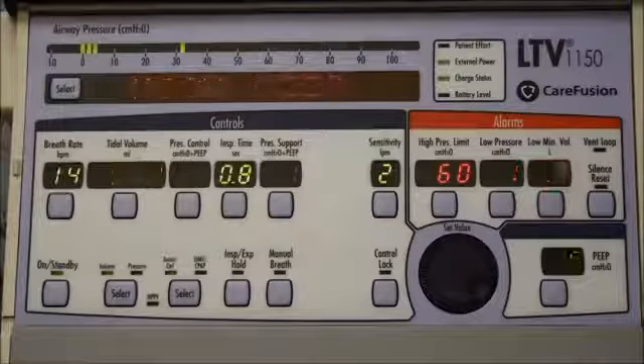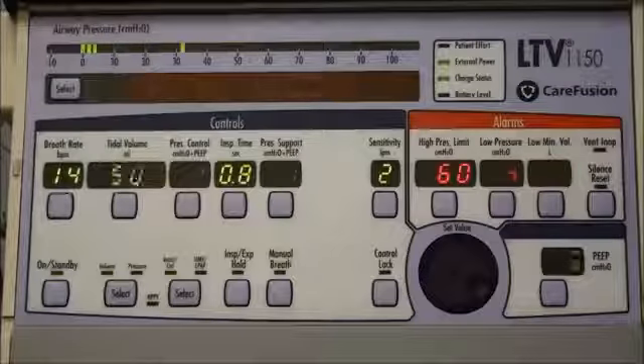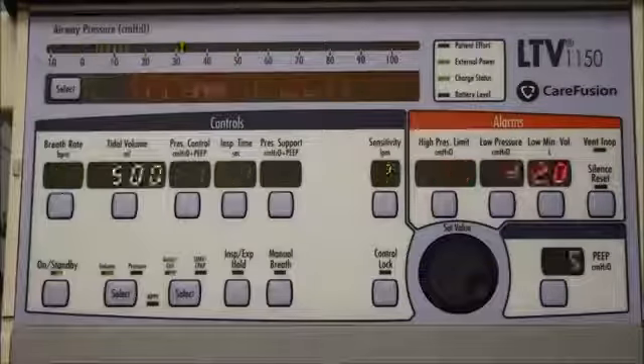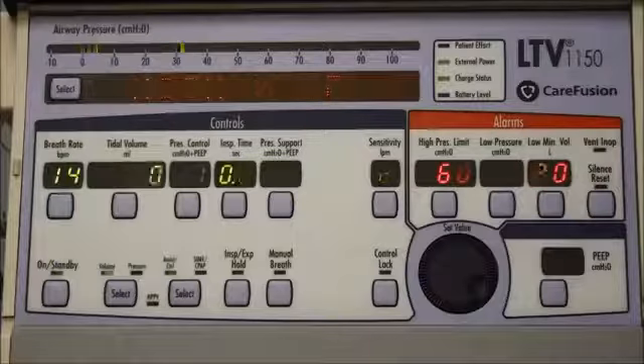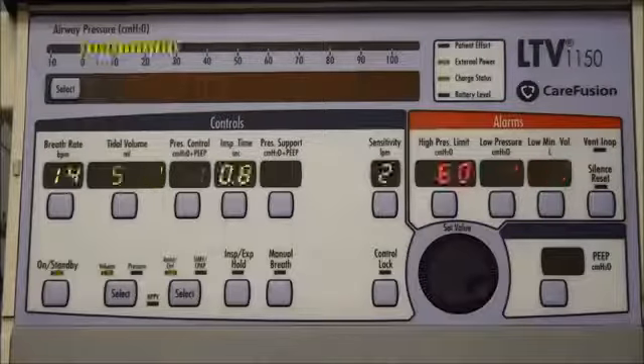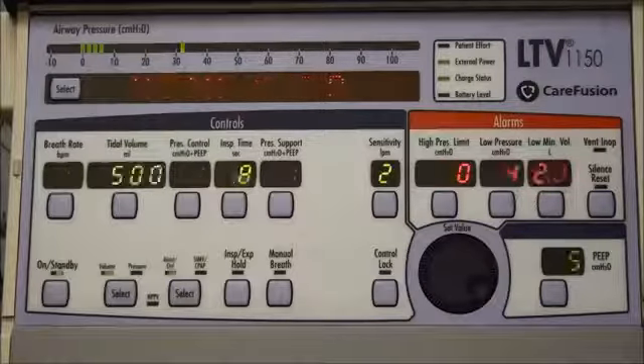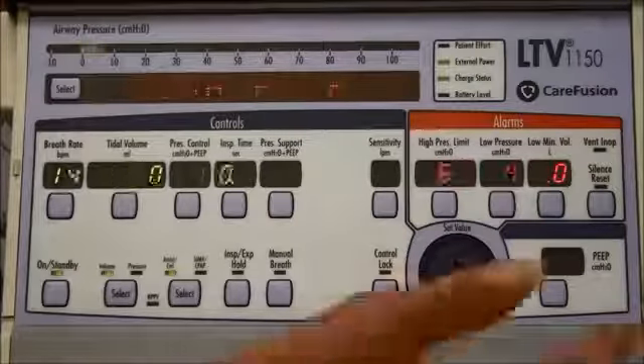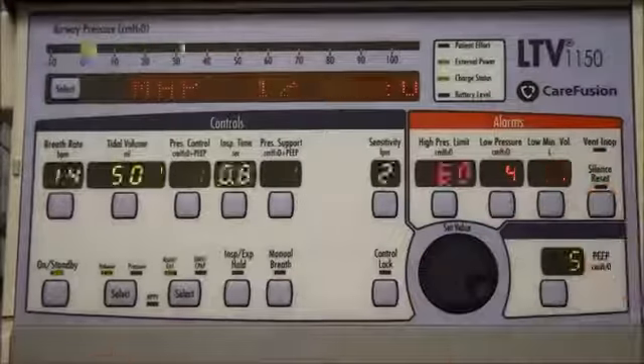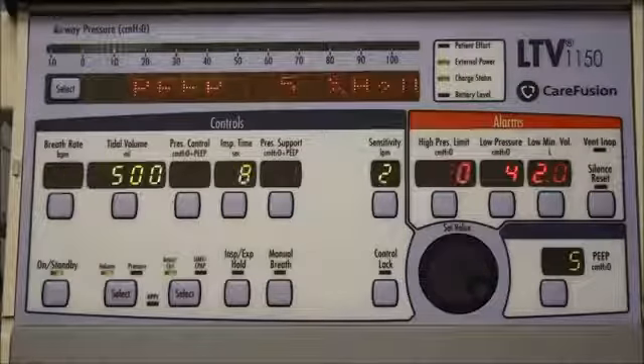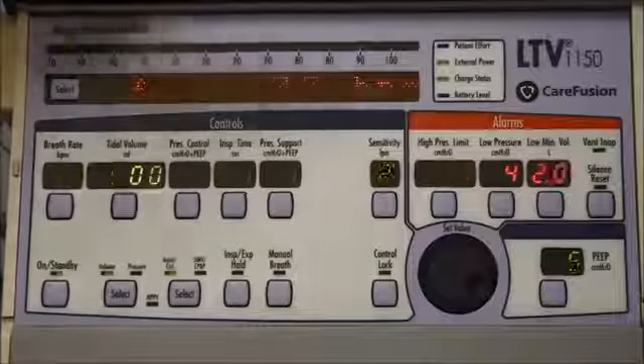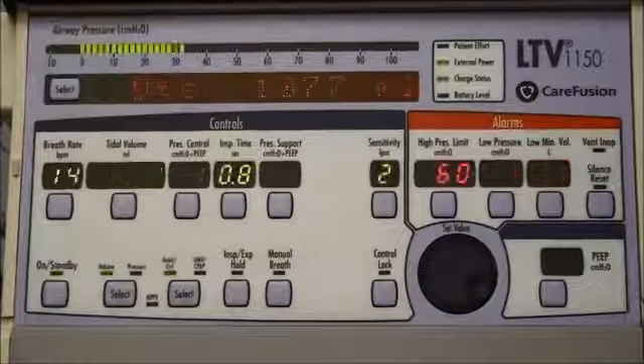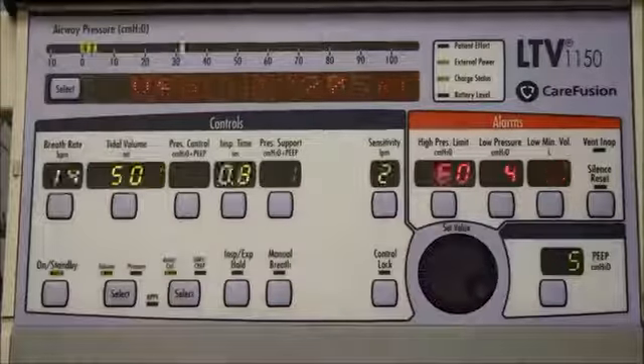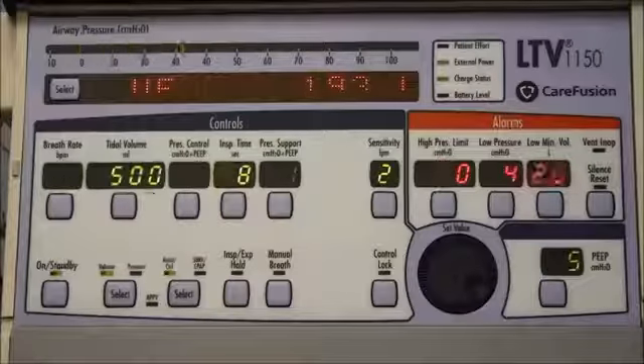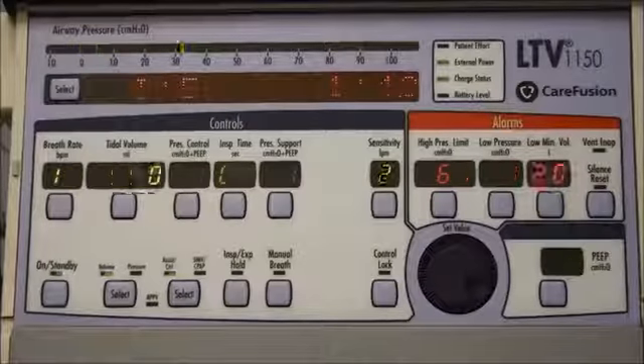So you saw we got a little bit of a high pressure and a high PEEP alarm. High PEEP alarm you don't see on the front here, but it was one of those other alarms that I was talking about. So what you can do now, it's done alarming and your pressure has gone back down below 60, so we know the problem is solved. So I go ahead and hit the reset alarm and everything just goes back to normal. If the pressures were staying up above 60, it would keep alarming. You would be able to silence that alarm for 60 seconds, but once 60 seconds was over, it would keep alarming. So that wouldn't really solve your problem.